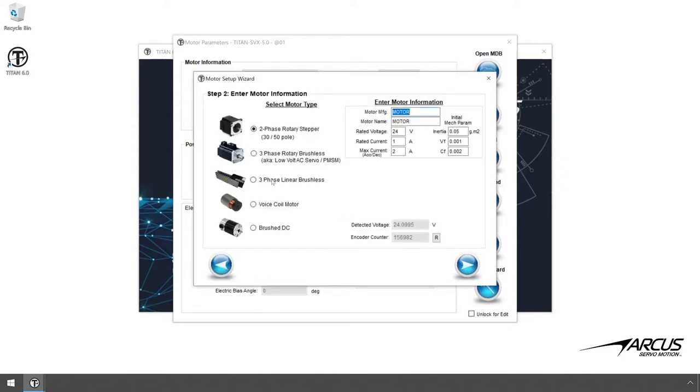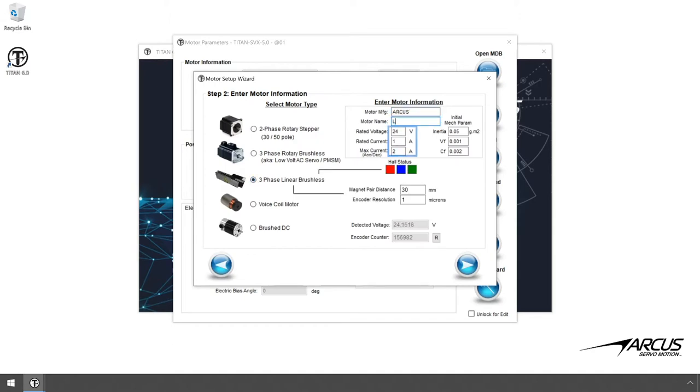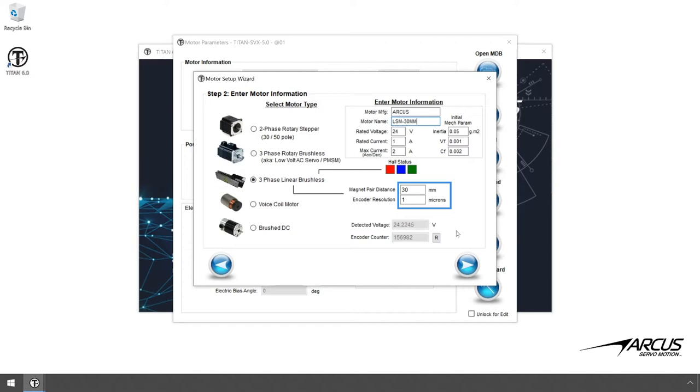Select the three phase linear brushless motor. Enter the motor manufacturer, motor name, voltage, rated current and max current for the motor. Then input the magnet pair distance and the encoder resolution for the motor. For this motor, the magnet pole pitch is 30mm and the encoder resolution is 1 micron.